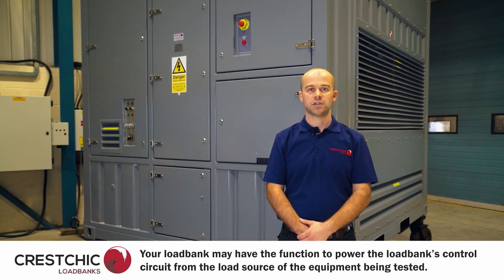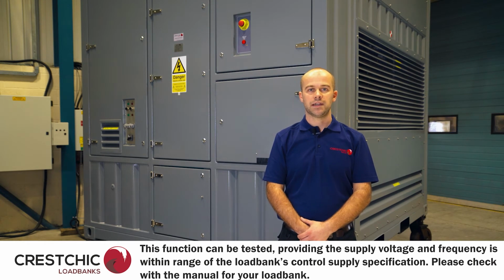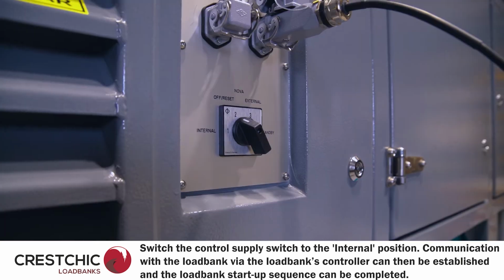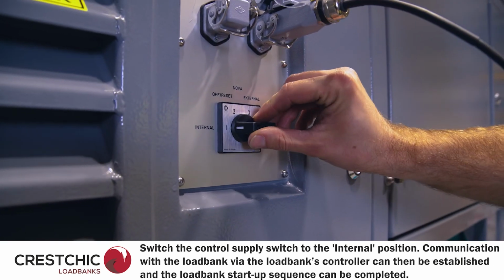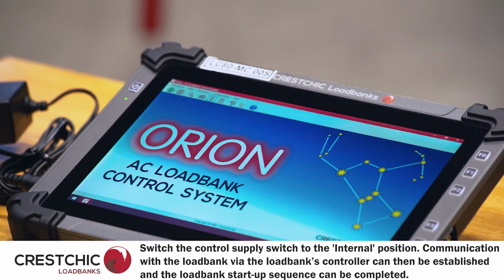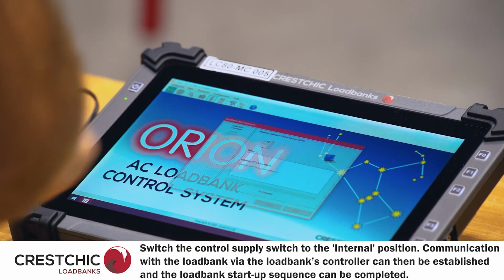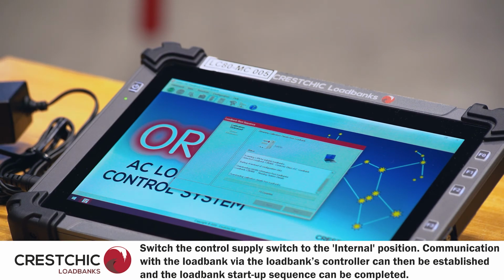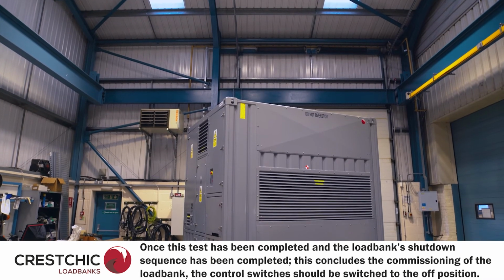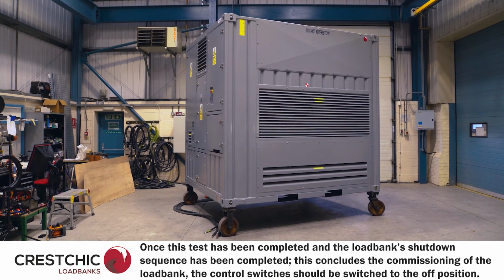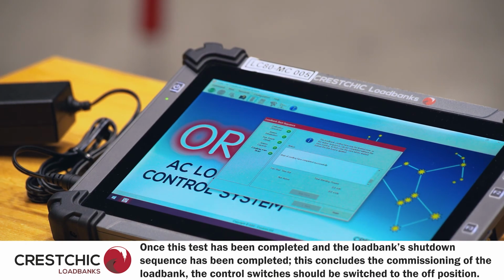Some load banks have a function to power the load bank's control circuit from the load source of the equipment being tested. This function can be tested providing the supply voltage and frequency is within range of a load bank's control supply specification. Please refer to the manual for your load bank. To test this function, switch the control switch to the internal position. Communication with the load bank via the load bank's controller can then be established and the load bank startup sequence can be completed. Once this test has been completed and the load bank shutdown sequence has been completed, this concludes the commissioning of the load bank.